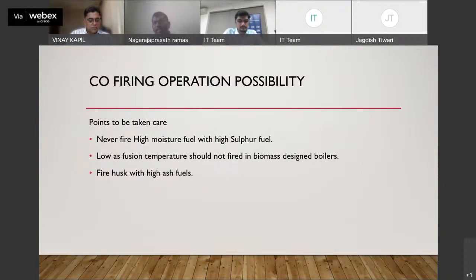And the possibility of co-firing of biomass with the fuel. What happens? Points to be taken care of when we fire high moisture biomass like bagasse or high moisture husk. You need to consider that sulfur should not be there with the co-firing fuels. If the sulfur is more, then there will be more possibility of corrosion in the downstream, like the air preheater and economizer inlet water cold zone. There will be a possibility of more corrosion.